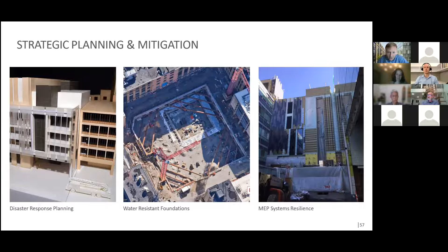There's even more. In fact, pretty much everything to do with this building is backed up. It's more like a redundant design than a resilient design in that aspect. We even have 2 sources for fire protection water, from MIT local and the city of Cambridge, and 3 sources of electricity from the central utility plant that Jacob talked about, the Eversource grid, and the emergency generator, plus 2 sources of steam and 2 sources of nitrogen.